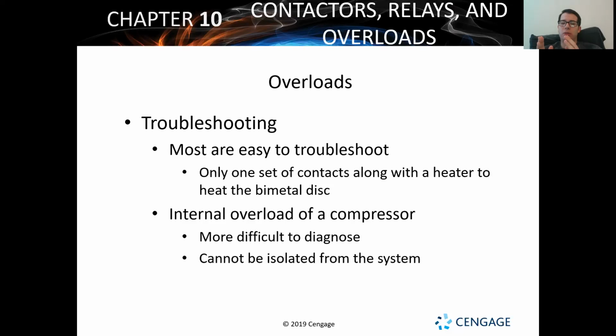You're looking at those internal overloads to make sure the internal overload is doing its job, but why is it overloading? So for an outdoor compressor, you're going to look at outdoor coils and airflow, and make sure the coil's not gunked up. If you feel like being a really weird dude, trust me, I do this every now and then because I'm crazy. I look at air conditioners. When I'm walking next to houses, I just casually look over. I'm not going up next to them and inspecting them, but while I'm walking my dog, I'm looking at condenser units.